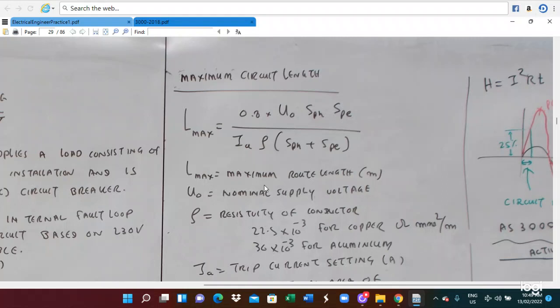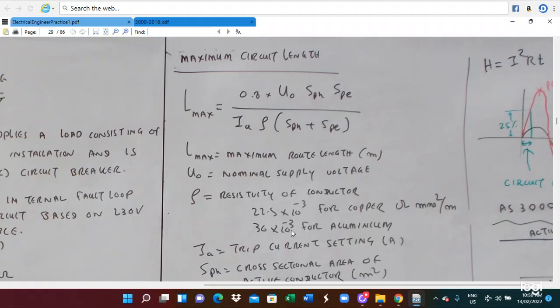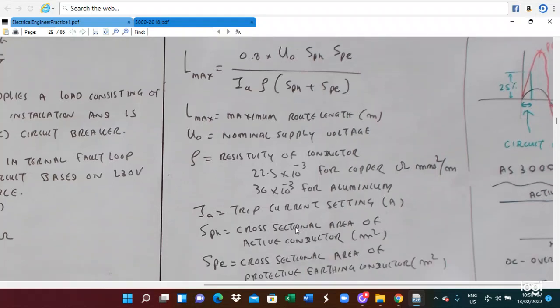So then you substitute, in this case, 22.5 into 10 power minus 3 for the copper conductor. The unit is ohm millimeter square divided by meter. And for the aluminum, 36 into 10 power minus 3. And IA is the trip current setting, in amperes. SPH is the cross-sectional area of the active conductor. And SPE is the cross-sectional area of the protective conductor.